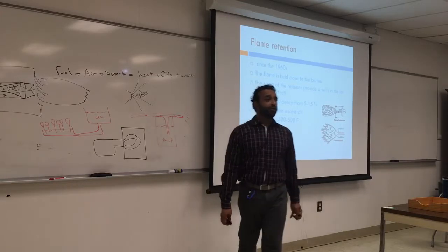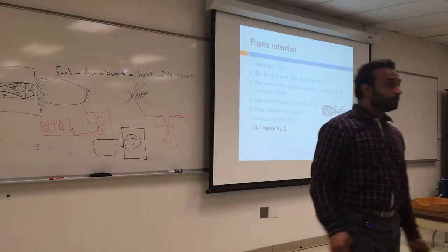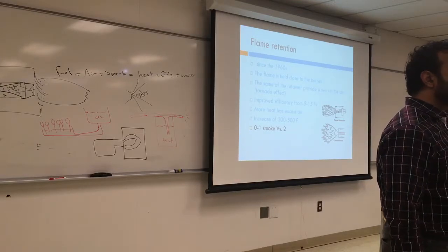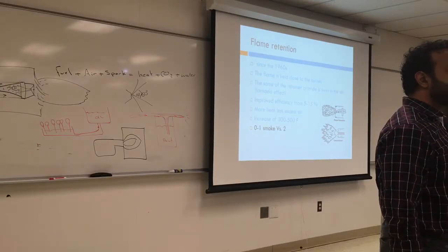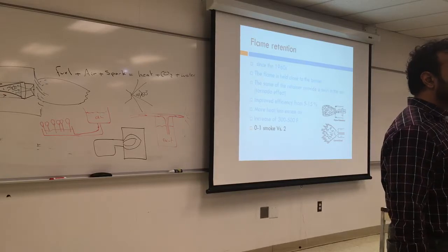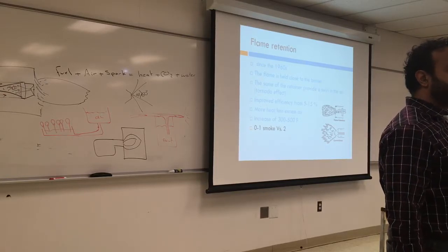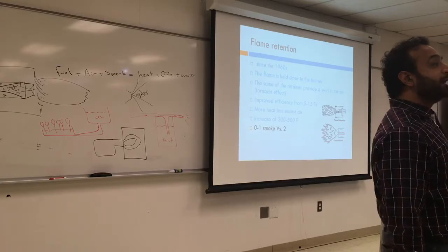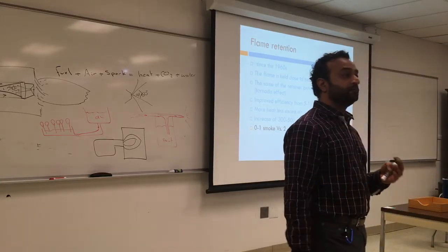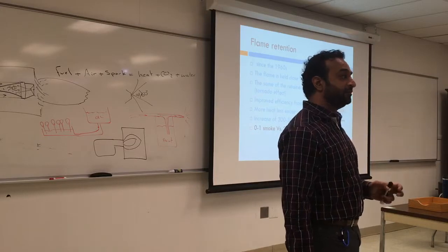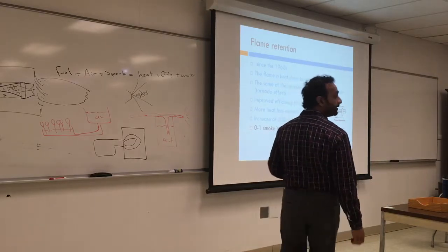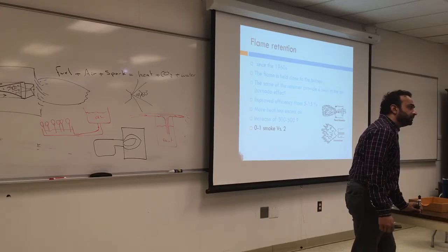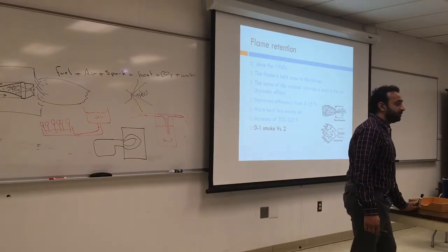What do you aim for when you go to do a tune-up now on an oil burner? How much smoke? What is your target? Zero smoke. You want zero smoke. If you run into a burner that was built in the 60s or 50s, probably you're going to have some smoke. And that's why the efficiency used to be 80, 70, and now we're aiming for 85 or even 90. But at this point, one smoke, it's not that bad. Depending on how old the burner is.